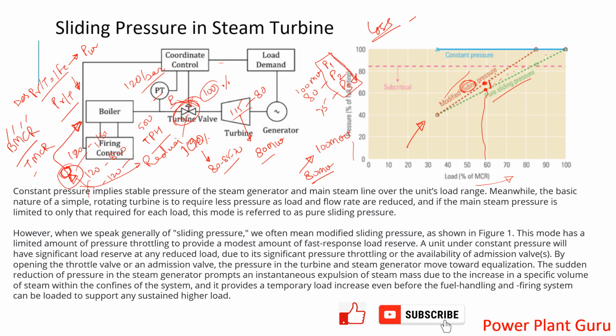So that is where the sliding pressure control has a problem to have a high ramp up. So to overcome this problem, the modified sliding pressure, which is this red line, is introduced. So this is how, on a very basic level, the sliding pressure and modified sliding pressure concept can be understood.